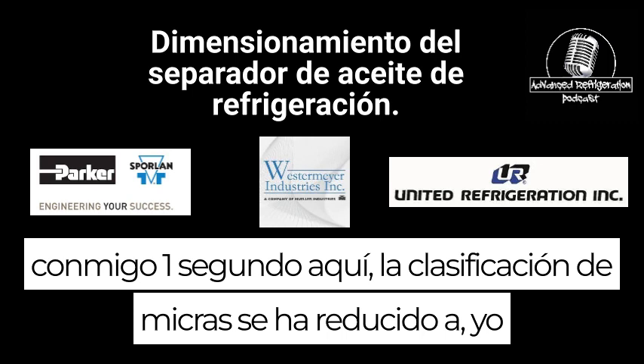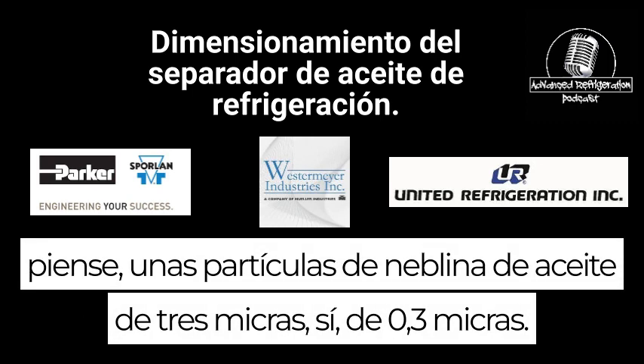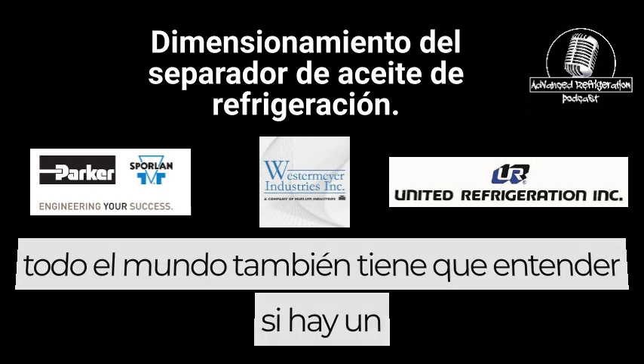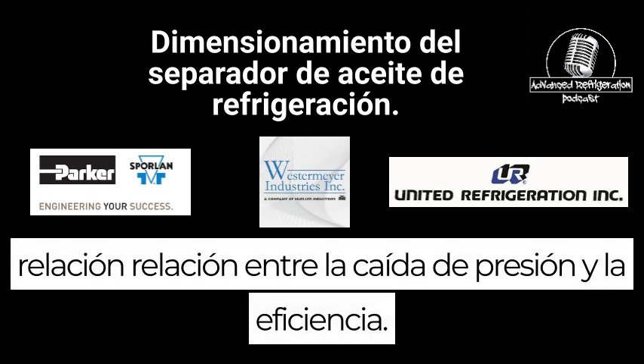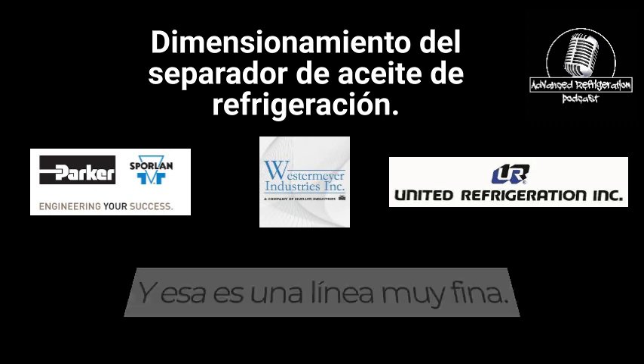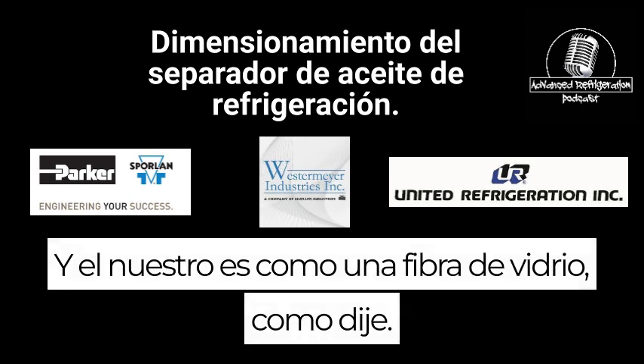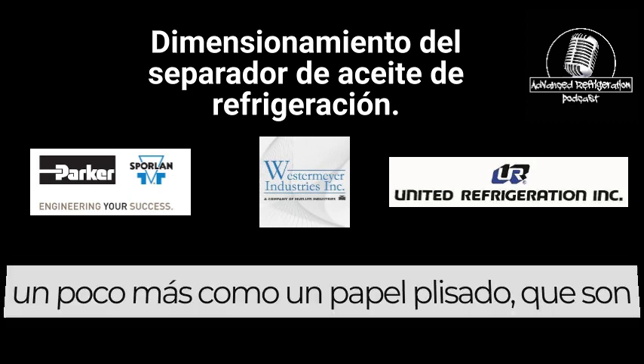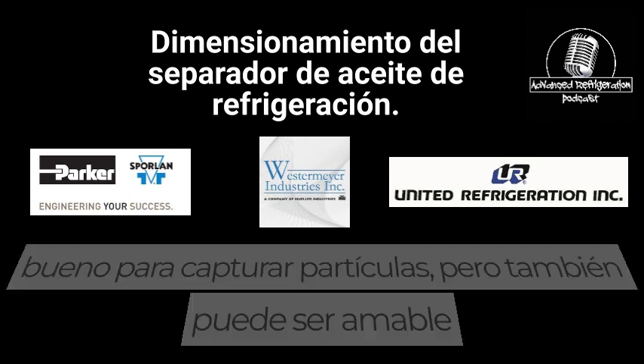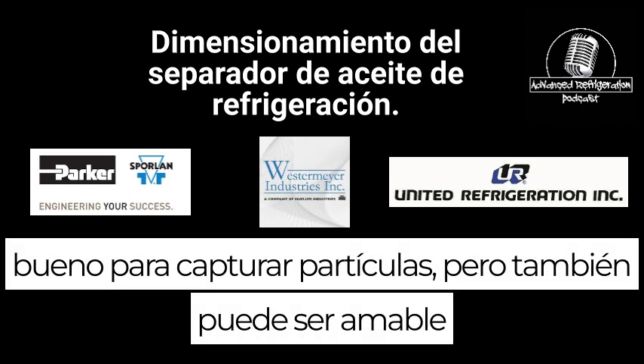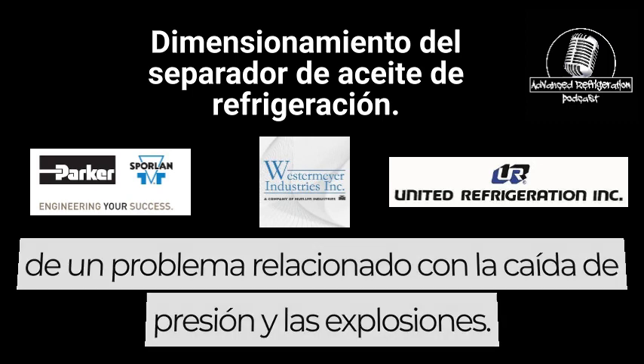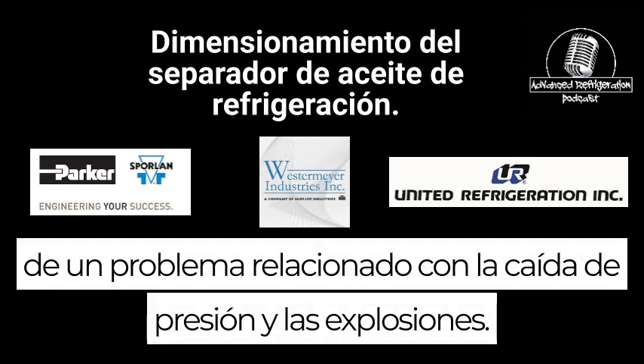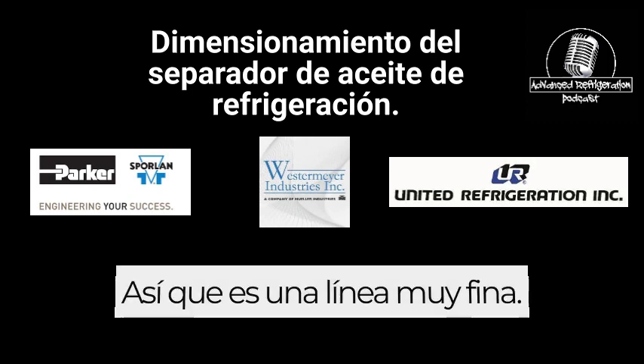But the micron rating is down to, I think, a 3 micron. Yeah, 0.3 micron oil mist particulates. And the big thing I think that everybody also needs to understand is there's a relationship between pressure drop and efficiency, and that's a fine line. Ours is like a fiberglass, like I said, and I think the Temprite models tend to be a little more like a pleated paper, which is good for capturing particulates, but can also be kind of a problem surrounding pressure drop and blowouts. So it's a fine line.